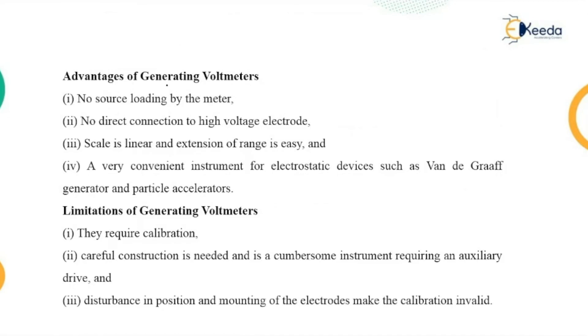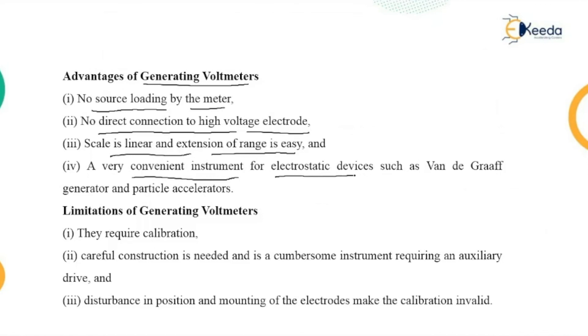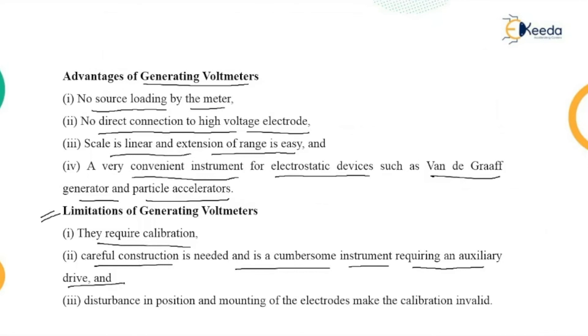Advantages of the generating voltmeter: no direct loading on the meter as it operates at low current; no direct connection to the high voltage electrode; the scale is linear and can be extended by adding resistance; it is convenient for electrostatic devices like Van de Graaff generators. Limitations include: it requires regular calibration, careful construction is needed as it is a cumbersome instrument requiring an auxiliary drive, and any disturbance in position or mounting of the electrodes invalidates calibration.